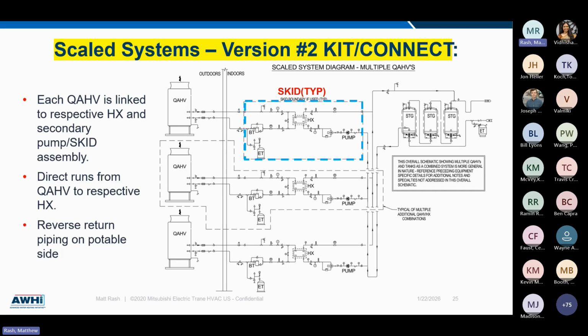The other two options are really identical in terms of control capability. This is what gives you higher degree of flow turn down, important for colder climates. It also incorporates more advanced controls for flow tracking between the primary and secondary. And that also brings in the ability for integrated COP monitoring capabilities that's part of that solution without having to go to additional custom controls. And that's offered in two versions, with the premier version being what we call the Connect, which is basically a skid platform where all those components are pre-assembled. That also gives you the added benefit of an included 10-gallon buffer tank and expansion tank for that primary glycol side. So that's all pre-packaged, pre-piped, takes all of that out of the hands of the contractor.